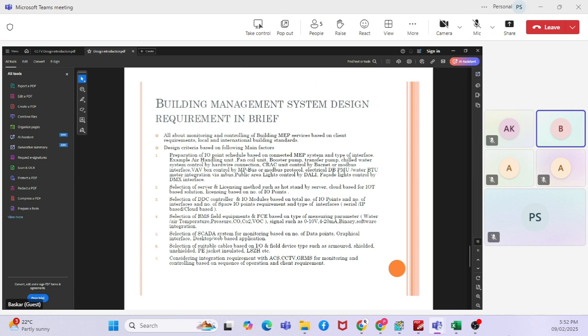The last point is the integration part. When integrating the BMS system with others like access control, CCTV, GRMS, or other systems, we need to know what kind of integration is required, hardware level or software level. If it's hardware level, only the hardware points are considered, like integrating the status of the NVR. For CCTV, NVR status can be taken as a digital input for the BMS. For GRMS, there's integration to know the status of guest rooms, and in case of any failure in the controller, that information is given at the hardware or software level. Similarly with access control, in case of controller failure, battery failure, or if someone opens the access control panel, an alarm can be given to the building management system. So it depends on the level of integration of other systems and the client's requirement, and the design has to be chosen based on that.